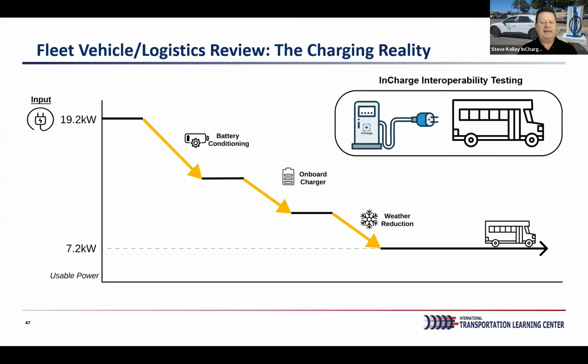When I mentioned thermal load management, using a level 2 charger in a bus means not all 19.2 kilowatts go straight to the battery, because the vehicle needs to keep certain onboard functions working while charging, like battery conditioning and, in cold environments, thermal loads that have to be managed. Those all pull power, and in some extreme situations we've seen this pull almost 11 or more kilowatts that's being used by the vehicle instead of going into the battery. Understanding what the vehicle actually uses for thermal load is critical, because it can extend your charge times by 2 to almost 3 times with that charger.